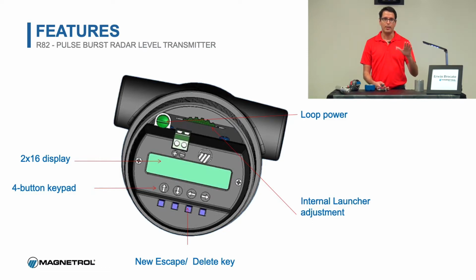It has a 4-button display. This is a more simplified design than the higher end models that have the full graphics display where you can do echo curves and the like. You can still do echo curves through the DTM, through a laptop or some kind of handheld communicator with this device. However, on the screen itself, it's a little bit more limited. I've configured some of these myself in the field, and it's not really that difficult. You have to learn how to use the DTM, but it isn't that hard at all to configure these devices.